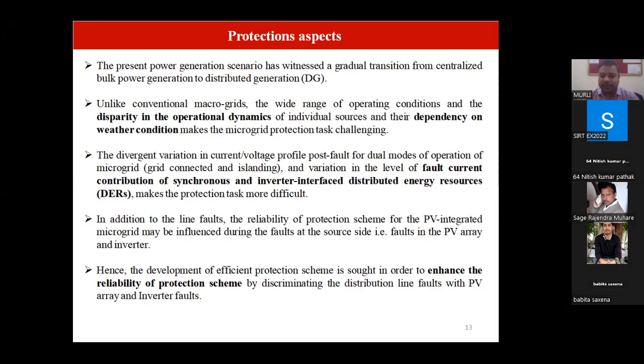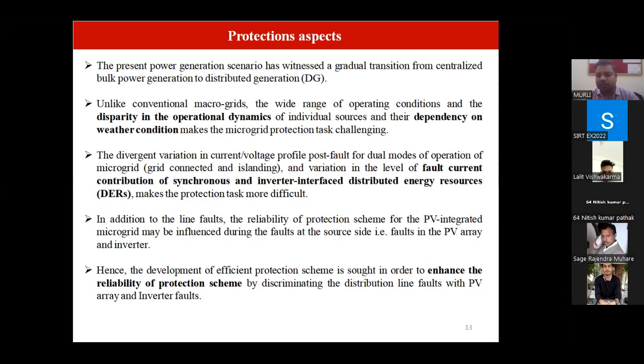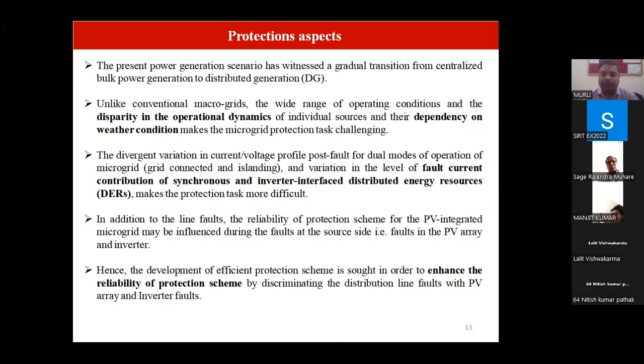Another thing is, we have different distributed energy resources and the fault current contributions are different. Synchronous generators have the prime mover, the rotor, so we have enough inertia to deal with minor stability problems. While if we talk of inverter-interfaced distributed energy resources, like solar, which is coupled with the inverter and the DC-DC converter, nowhere do we have inertia. We don't have any moving part. So the level of fault current contribution is very much limited. In synchronous generators, we can go up to 5 to 6 times the rated current, while in inverter-interfaced distributed energy resources, it's limited to only 1 to 1.5 times.